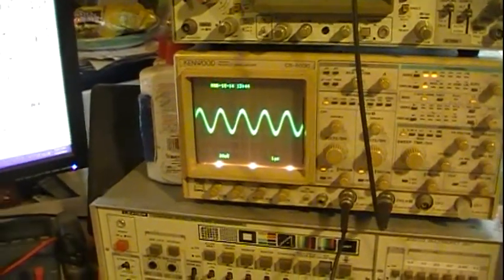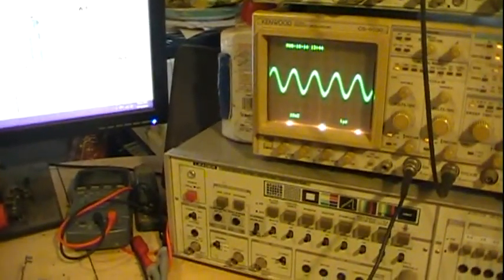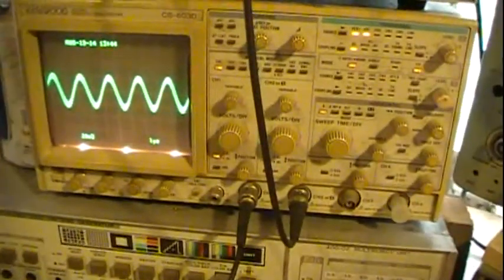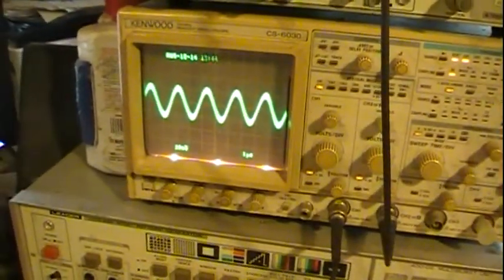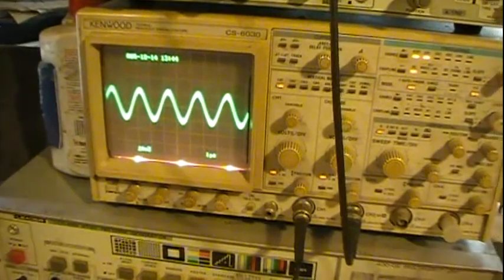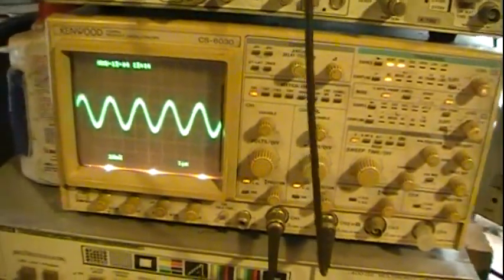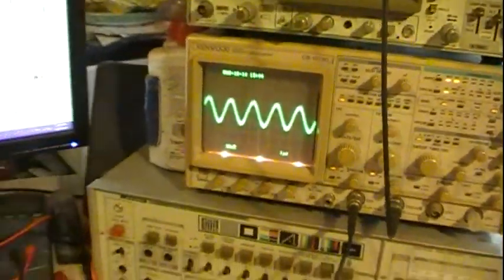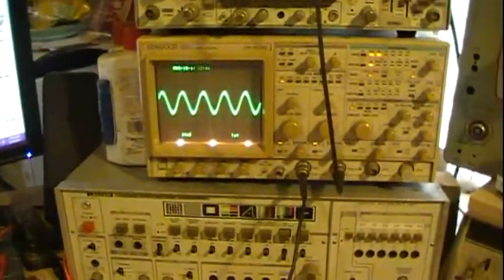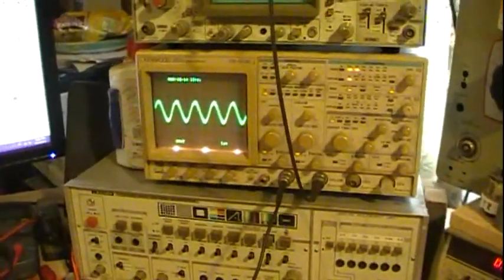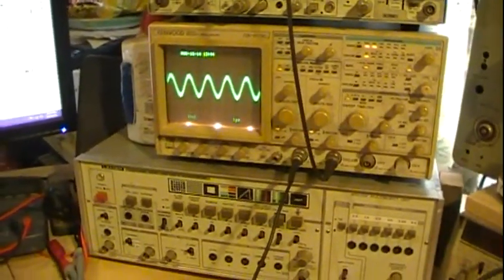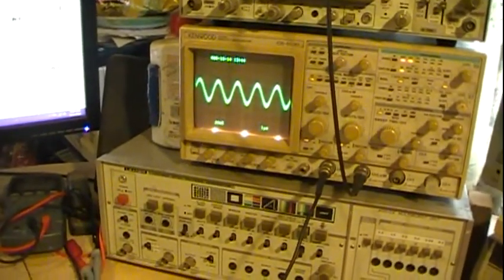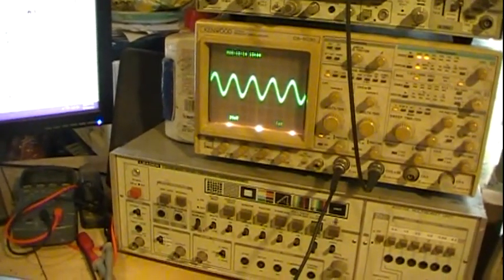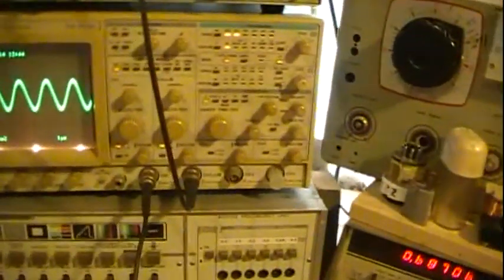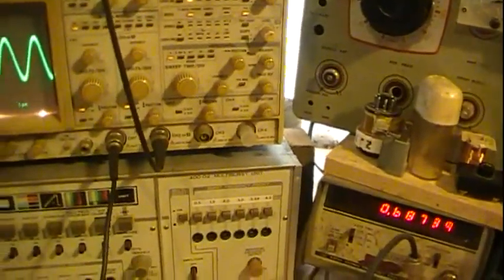In order to really test it and check it, you need to go back up to the grid and feed into the grid, and that's where you can find your true peak, or at least get pretty close. Now again, you may have a double peak, a lot of them do, but I'll show you what happens. It should peak out somewhere around 380 or so. We're going to start taking it down.